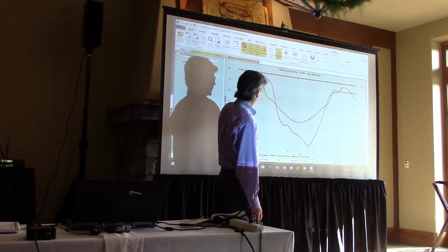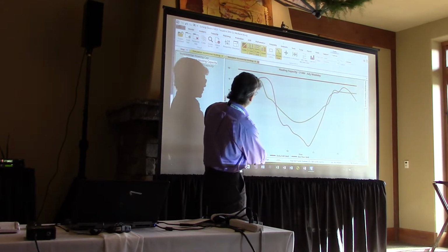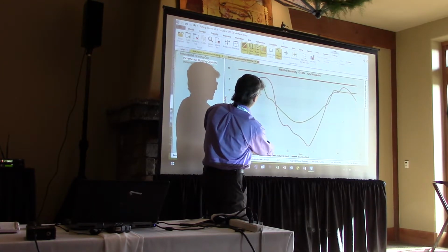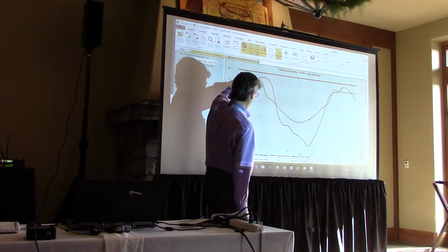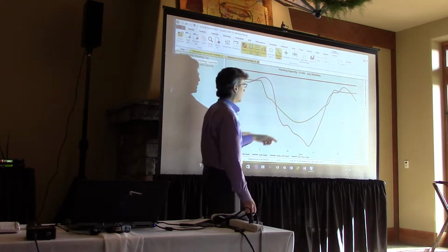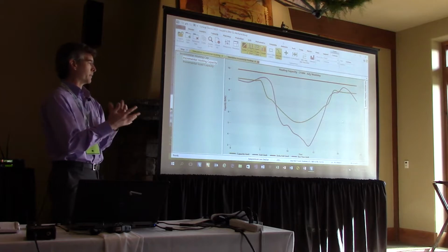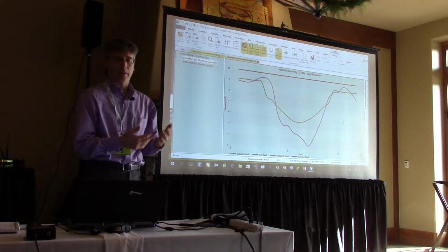And so reverse flow, like right here, you can see from 4 to 8 o'clock in the morning, it's going to be a thermal problem. And later in the day, it's a reverse flow problem. And that's, you know, the load and the generation are tied together. You know, it's a dance that's going on there.